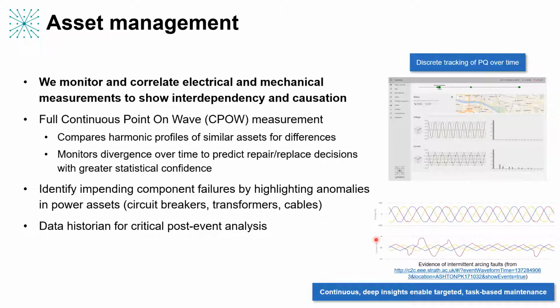PMUs, phasor measurement units, and synchrophasors give you a time-stamped phasor measurement, which is an amplitude and a phase at a particular point in time. The way the standard defines it is you've got a point in time, and from the last cycle, say, you've calculated your phasor. You've got a sinusoidal wave, and you give the amplitude and the phase of that. But you've thrown away quite a lot of information in doing that. You've given away information on the harmonics. You might have captured a few discrete harmonics, depending on the standard you're working to, but you've thrown away the rest, certainly the majority of information, certainly transients.